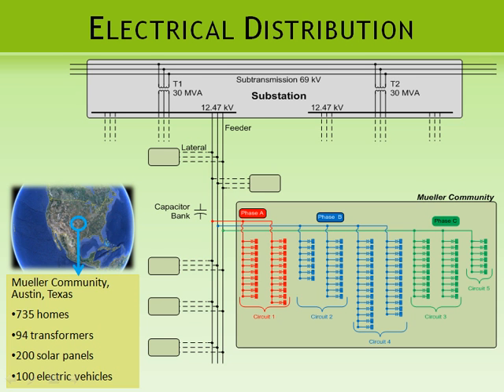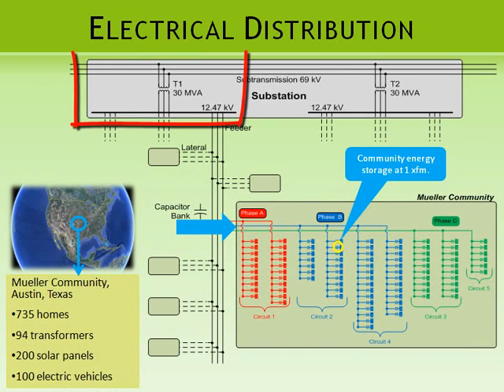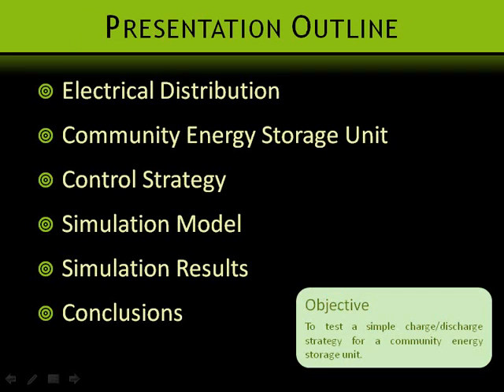This is the electrical distribution system for a residential community in Austin, Texas. The entire community is fed radially from one lateral, where each phase serves 20 to 40 transformers. The storage unit will be installed alongside one of the 94 transformers. This shows that the impact of the storage unit will be small as seen from the substation. However, there may be advantages for the homes downstream of this particular transformer.